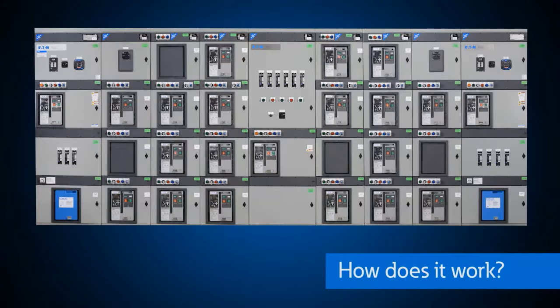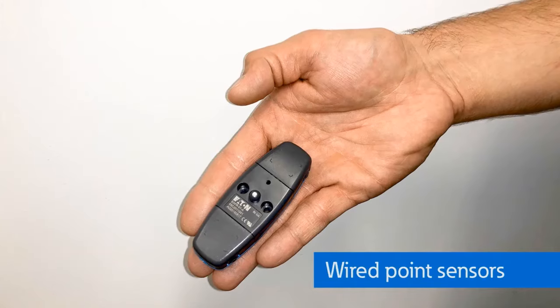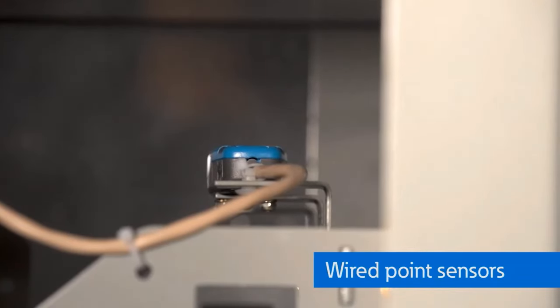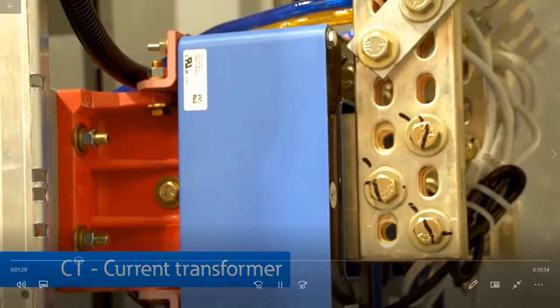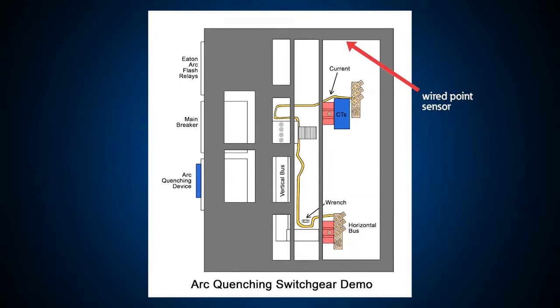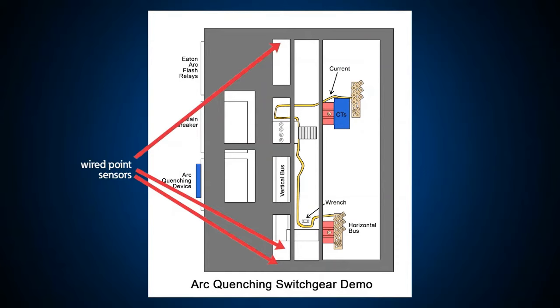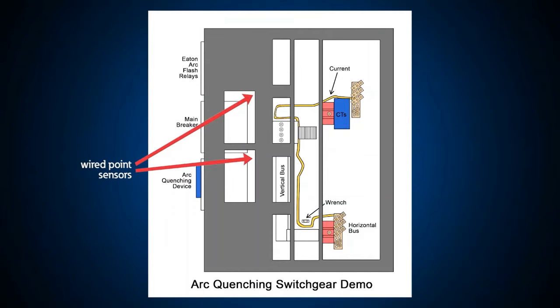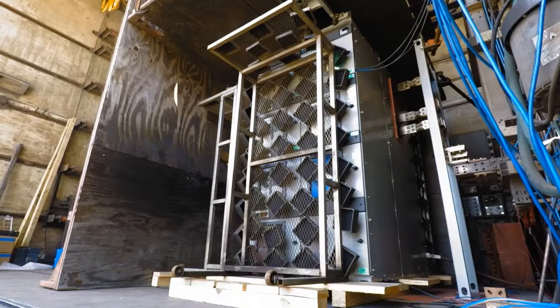In a typical lineup of arc quenching Magnum DS low voltage switchgear, we utilize wired point sensors installed throughout the equipment that will detect the flash of light from an arc flash. And we also use CTs on the incoming line that will detect a rise in current during a fault. You can see a point sensor up at the top of the incoming cable compartment, for example. There's also one at the bottom. There are 3 more point sensors located in the bus compartment and, importantly, point sensors located over the finger clusters of all of the draw-out devices. The locations of these point sensors are tested and validated at a high-powered test lab during actual arc flash events, so we know that regardless of where an arc flash initiates inside the switchgear, we'll be able to detect it.